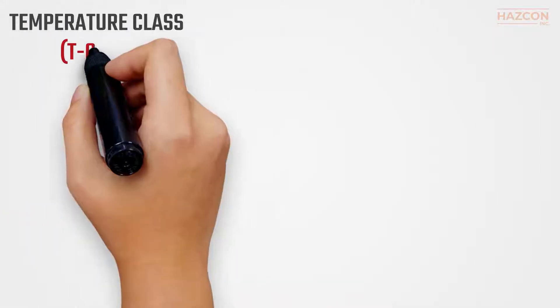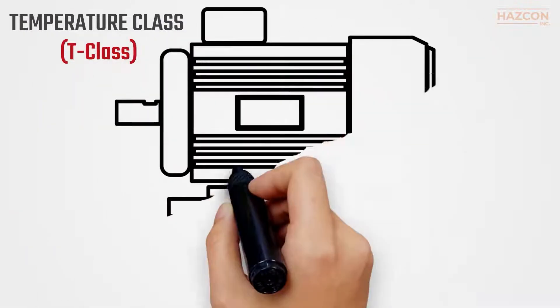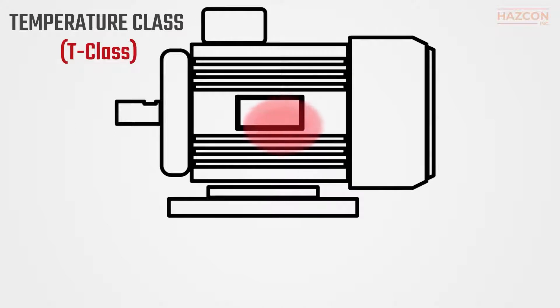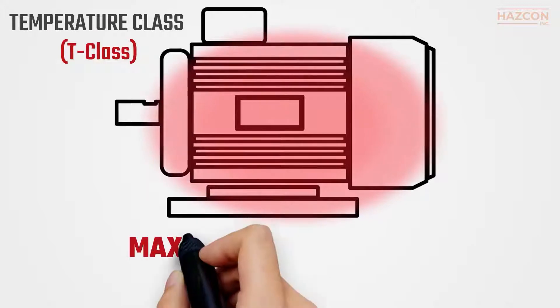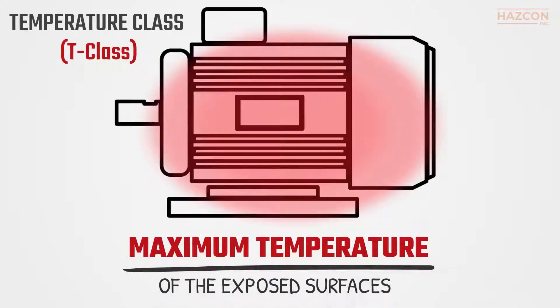Temperature class, known as T-class, is one of the characteristics used to classify an electrical device so it may be safely installed in a hazardous location. It is the maximum temperature of the exposed surface of the electrical apparatus, based on the ambient temperature range allocated for that device.